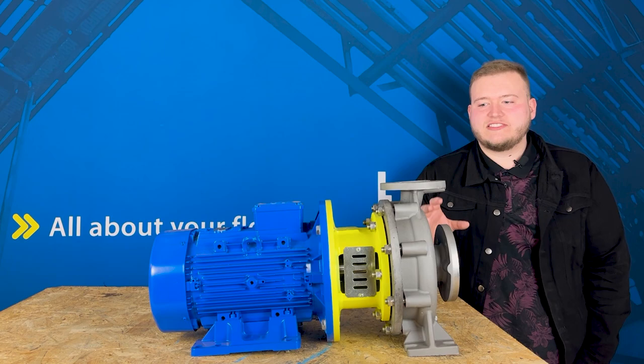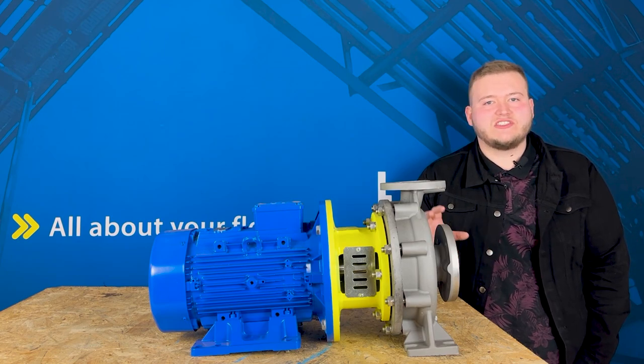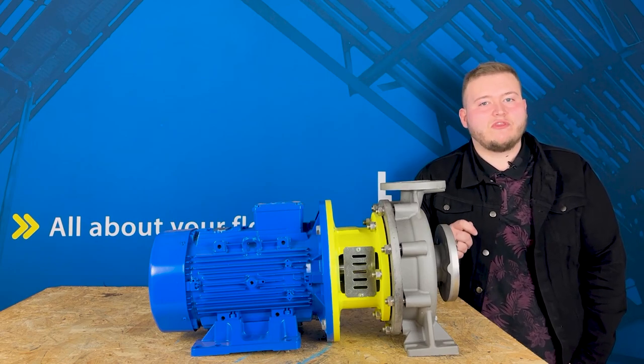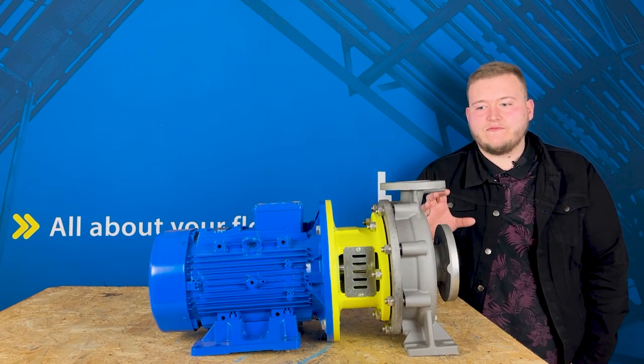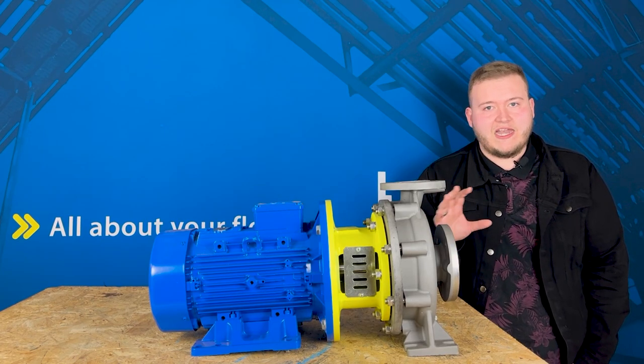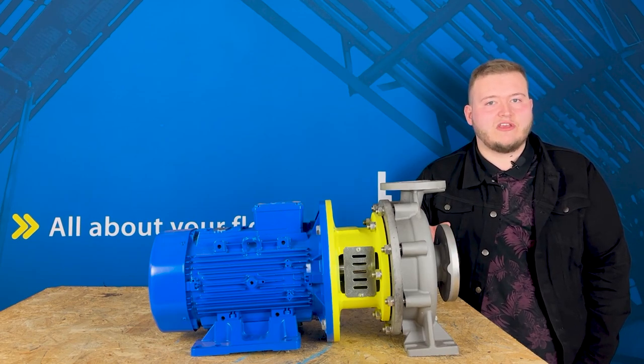These are centrifugal pumps, single stage end suction, that are built to EN733 norm. EN733 norm means that the volute casing is built to a certain dimension tolerance, so they're face-to-face compatible with any other pumps built to that EN733 norm.